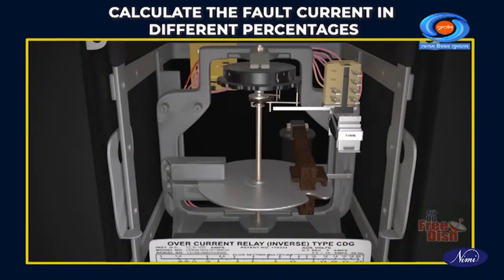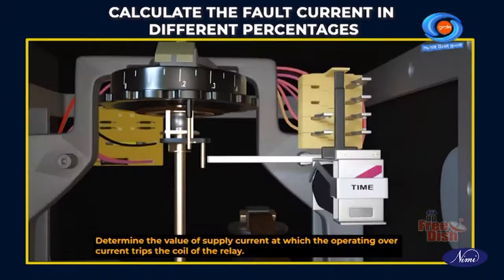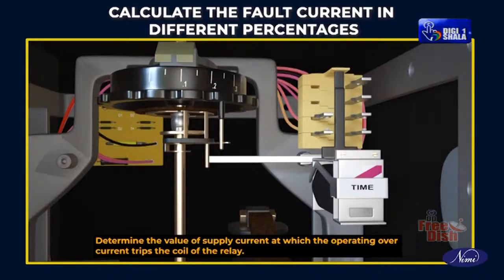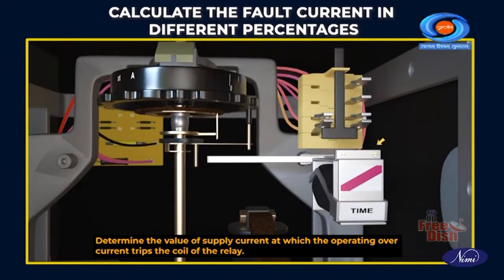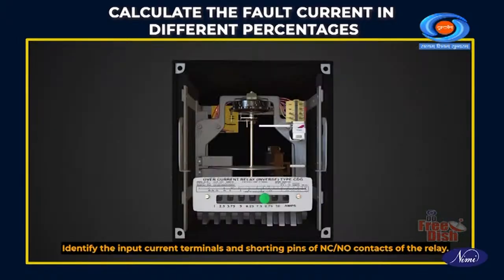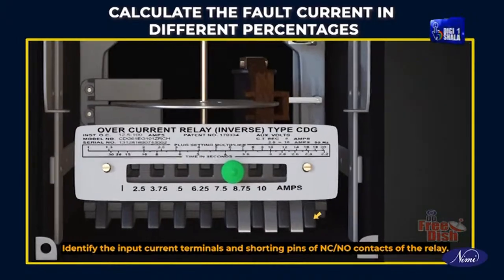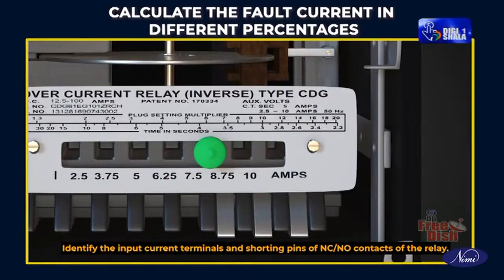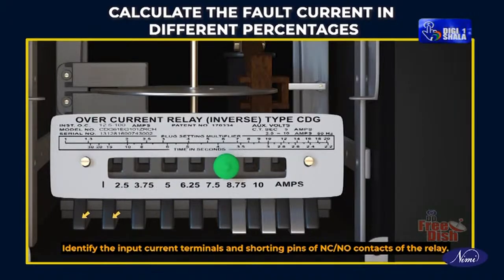Calculate the fault current in different percentages. Determine the value of supply current at which the operating overcurrent trips the coil of the relay. Identify the input current terminals and shorting pins of NC or NO contacts of the relay.